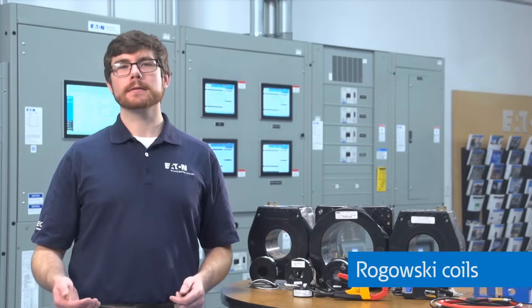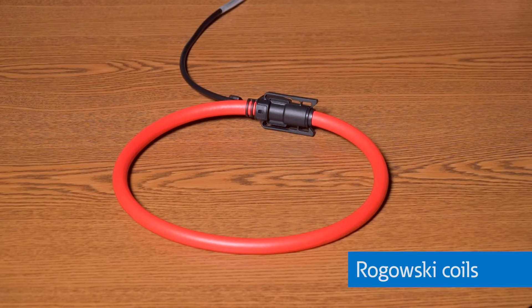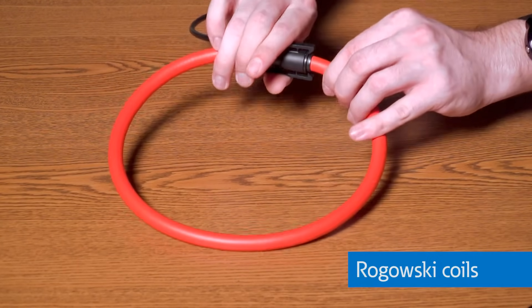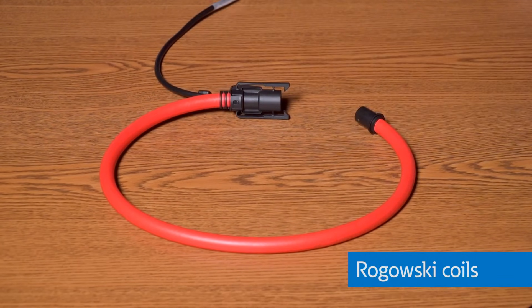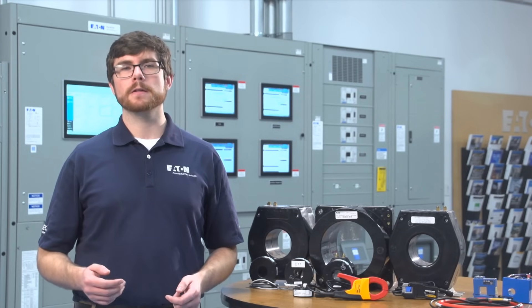Many multimeters utilize a combination of CTs and Hall effect sensors in order to get an accurate current measurement. Finally, Rogowski coils are an open-loop current transformer using an open-air core with a very low inductance that is capable of measuring very fast transient currents and AC currents. Due to the low inductance, the signals that Rogowski coils generate are very small and require amplification and a DC power supply like a Hall effect sensor.